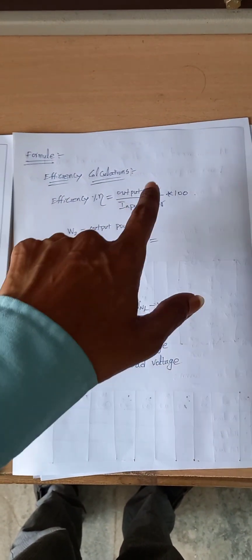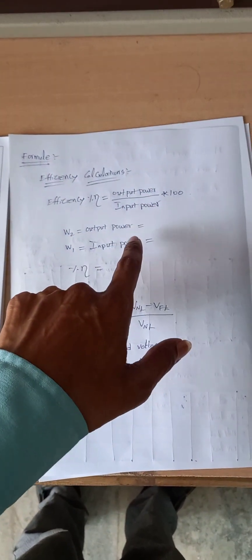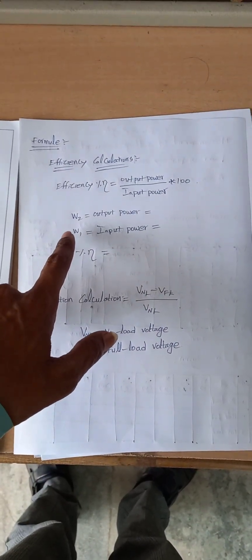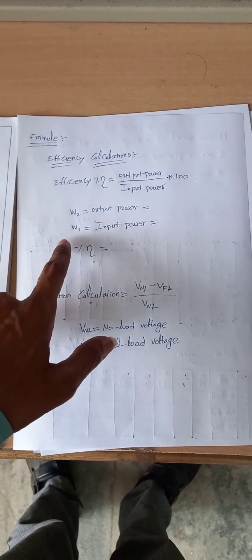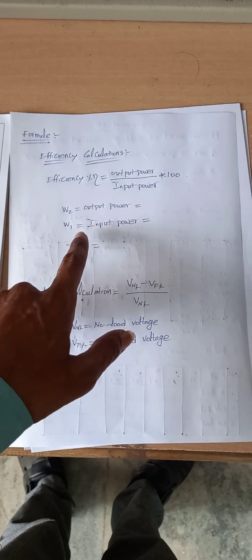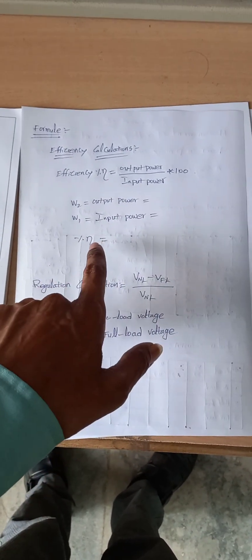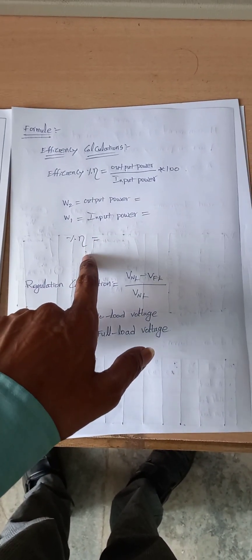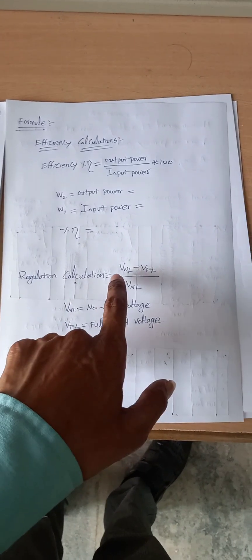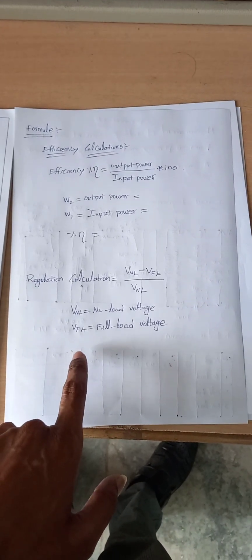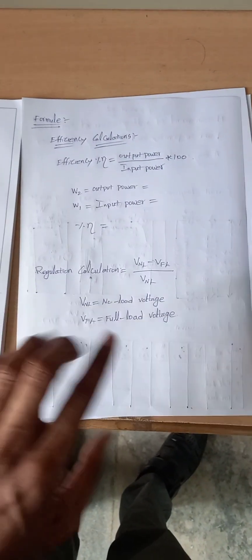Efficiency is equal to output power divided by input power, into 100. W2 watt meter power is the output power and W1 watt meter power is the input power. After taking the readings we will calculate efficiency, and regulation is equal to no load voltage minus full load voltage, divided by no load voltage.